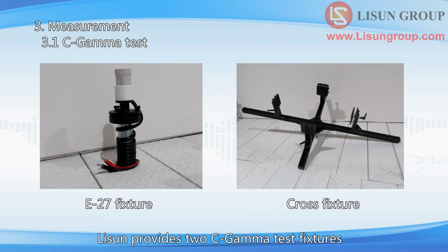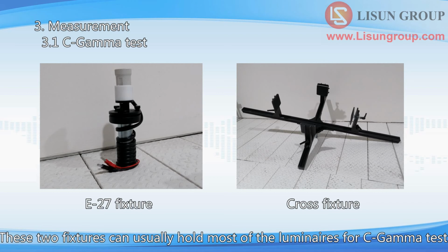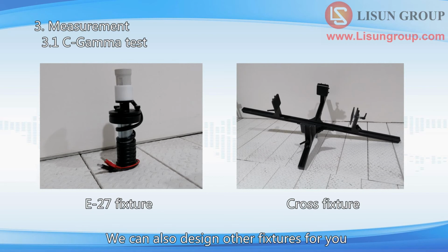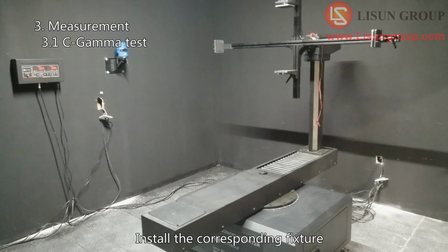Lisun provides two C gamma test fixtures: E27 bulb fixture and large cross fixture. These two fixtures can usually hold most of the luminaires for C gamma test. We can also design other fixtures for you if you have special luminaires to test. Install the corresponding fixture to the horizontal axis of the goniophotometer.